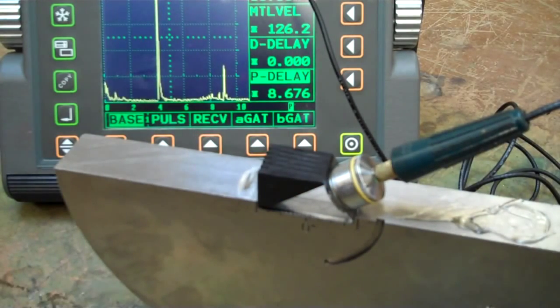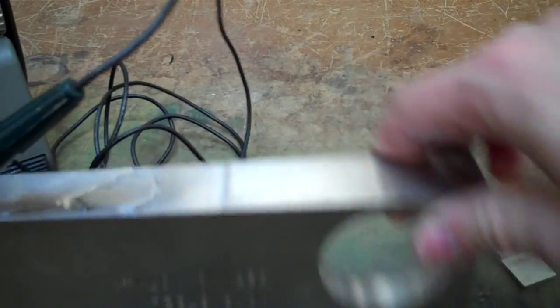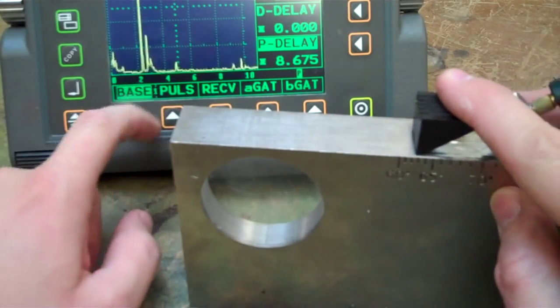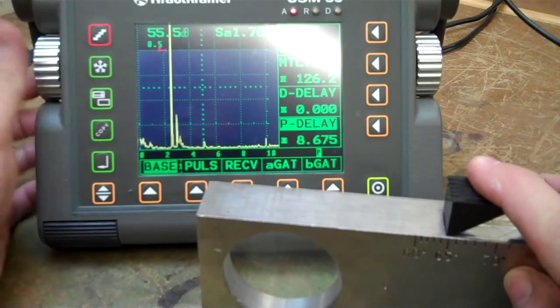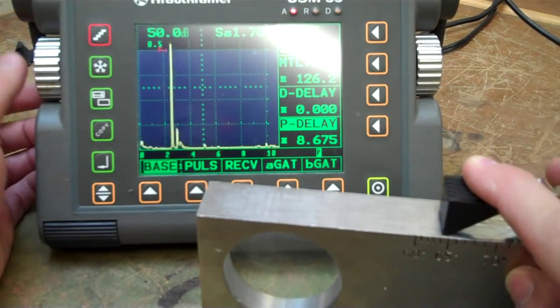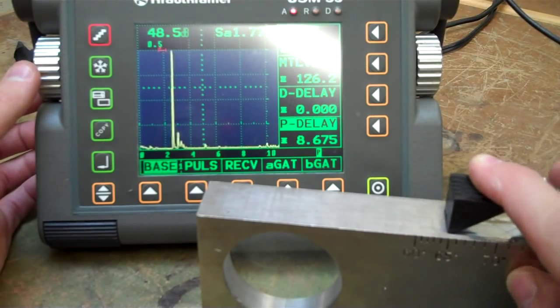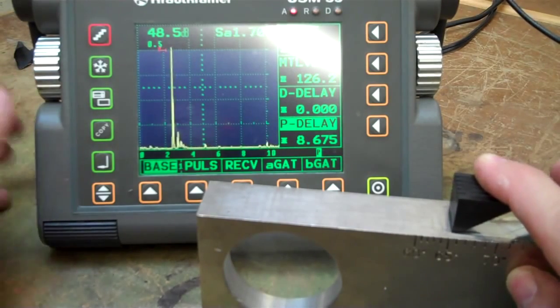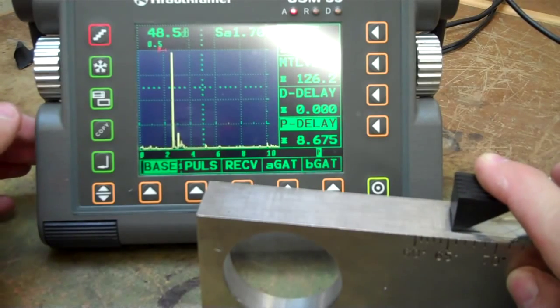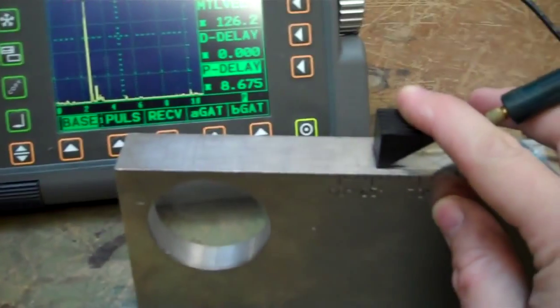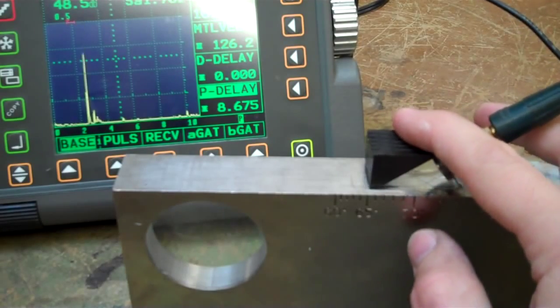So that's part 2. Now, part 3 says verify the refraction angle, which is on this side. So we're going to set that thing over the 70-degree mark. Let's turn it around here. There's 60, 65, 70, and point it towards this plexiglass disc. Okay, so we're doing that. We're just looking at this signal here. It doesn't have to be perfect. Okay, we can bring the gain down some. Just looking at where this thing's peaking up at. Peaking up about right there. Look down. It needs to be right over the 70, which it's pretty close. So now we know our transducer is refracting out at 70 degrees, which is good.